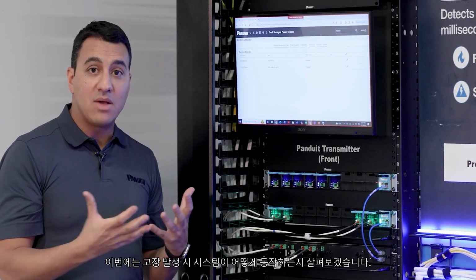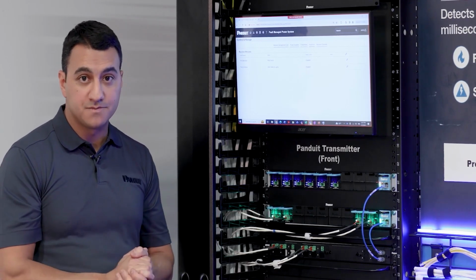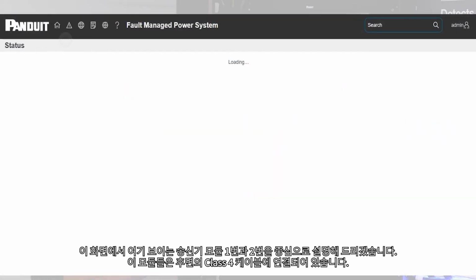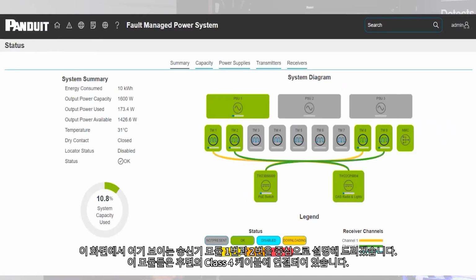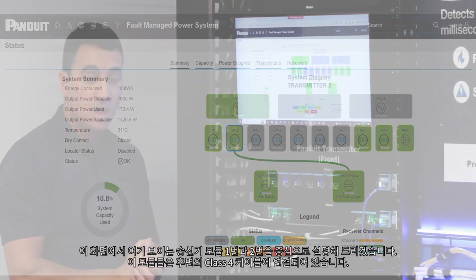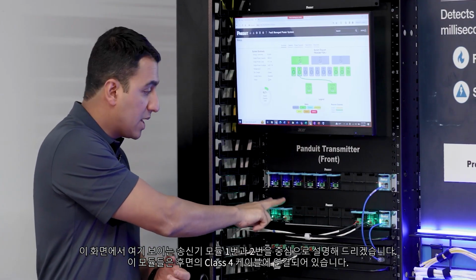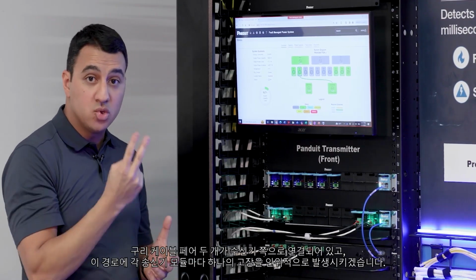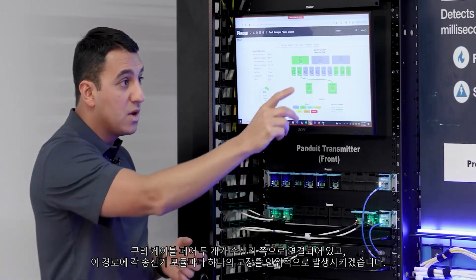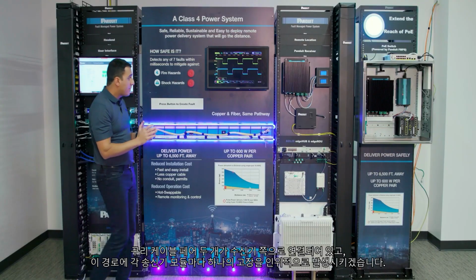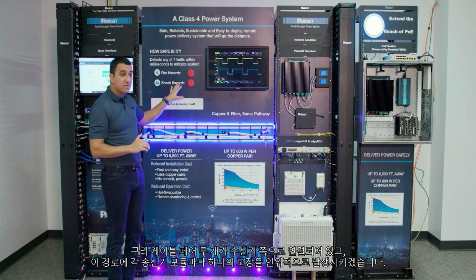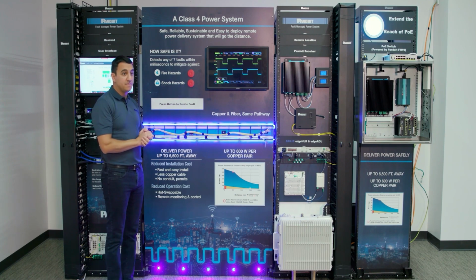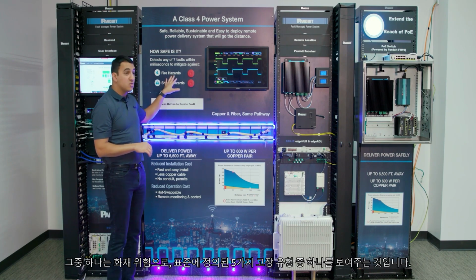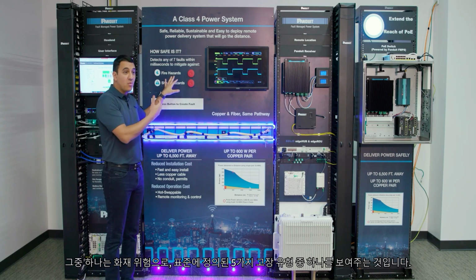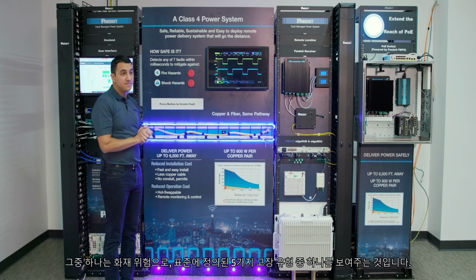Now let's take a look at how the system behaves when a fault occurs. Going back to this screen here, I'm going to focus more on transmitter modules 1 and 2, which are right here. And those are connected to a class 4 cable in the back, so 2 pairs of copper cable running out to our receiver. And in that path, we're introducing one fault for each of these transmitter modules. One of the transmitter modules is connected to a fire hazard, we're showing you one of the 5 different faults that are in the standard.